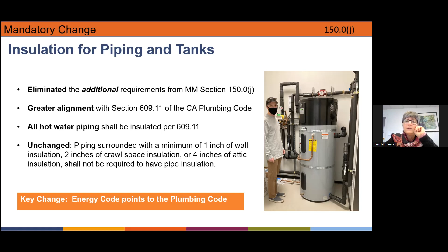Now our energy code references the plumbing code. I put an excerpt here so you can have it handy in case you're reading one code but not the other. The main takeaway is that for small pipe sizes under 2 inches, which we usually see in domestic hot water situations, the insulation thickness around your pipe has to be the same as the diameter. So for a half inch pipe, that comes out to about R3 to R4 worth of insulation—it's a quality insulation product.